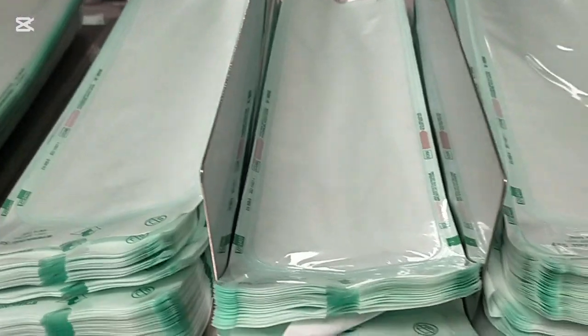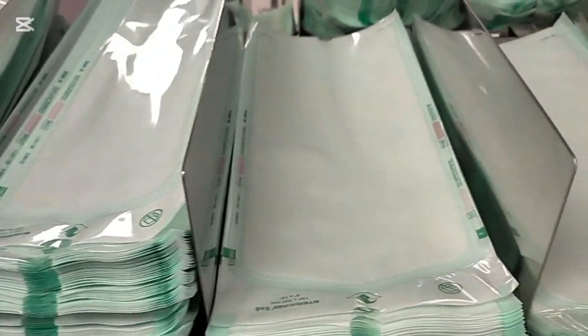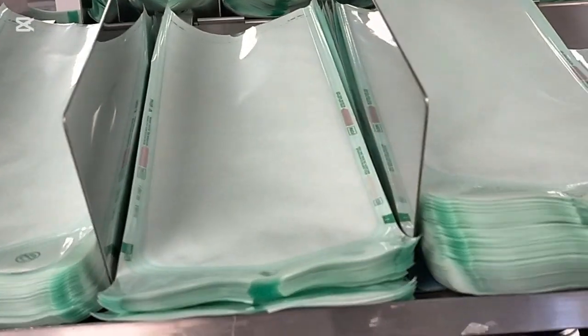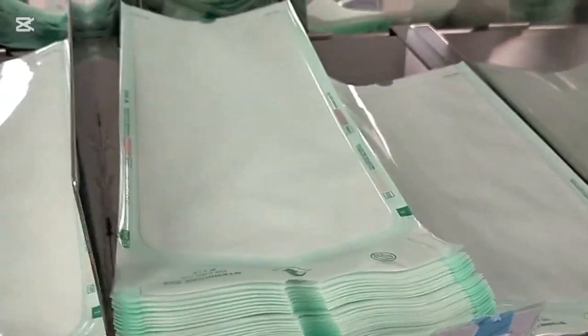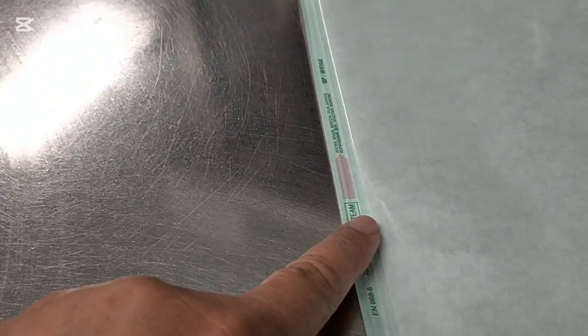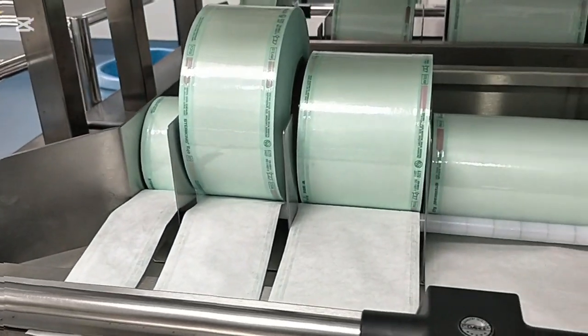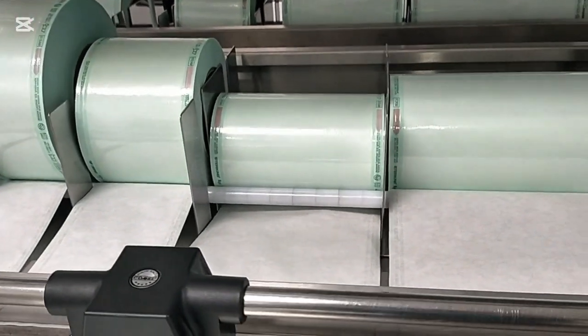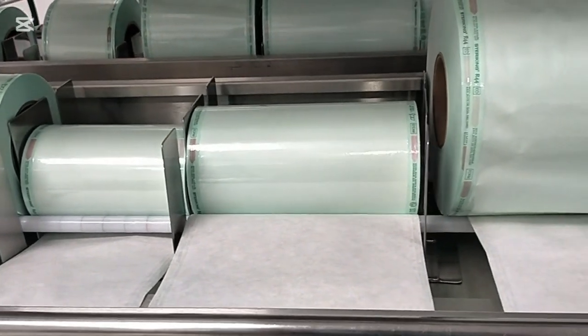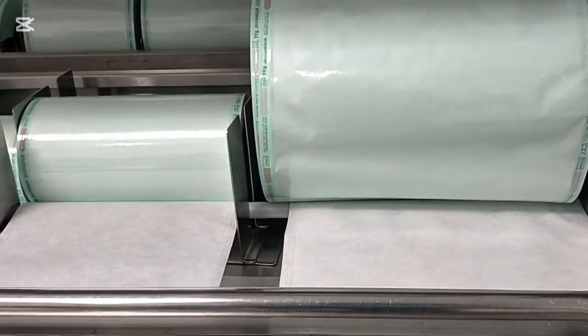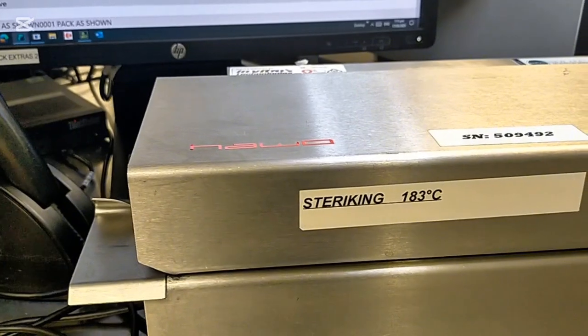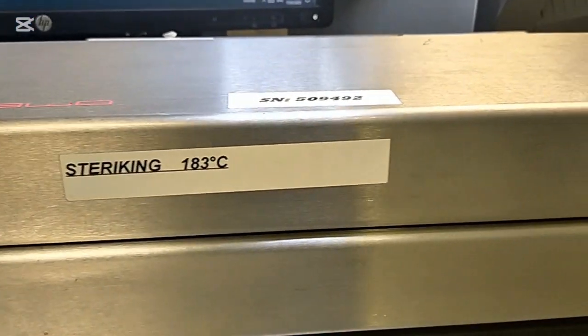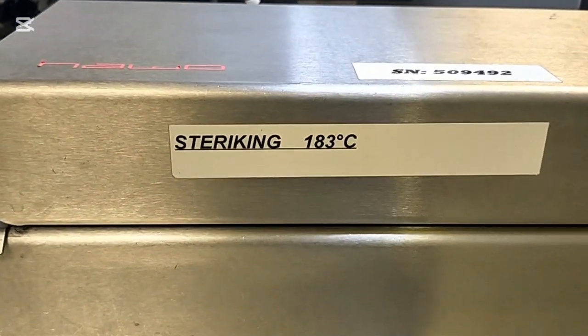So these are the pouch that we're going to use for steam sterilization. We have pre-cut in different sizes, which is easy to use. Remember the process indicator? This is what it looks like. It is built inside the pouch and can be found on the side. This is the reel form. We use this to customize according to the size of the device. Our heat sealer is 183 degrees Celsius, so we are within the range.